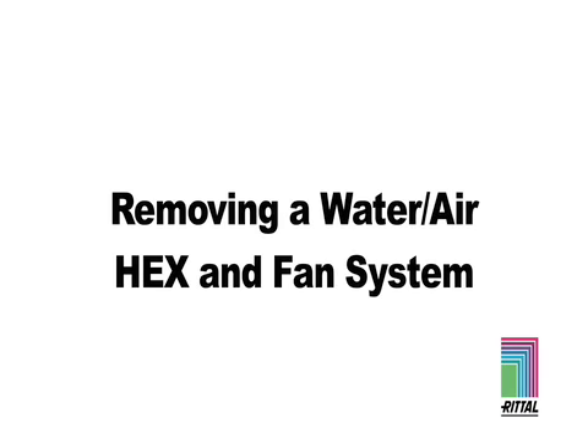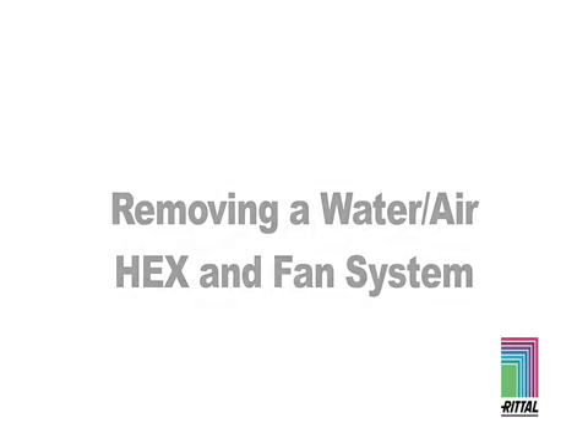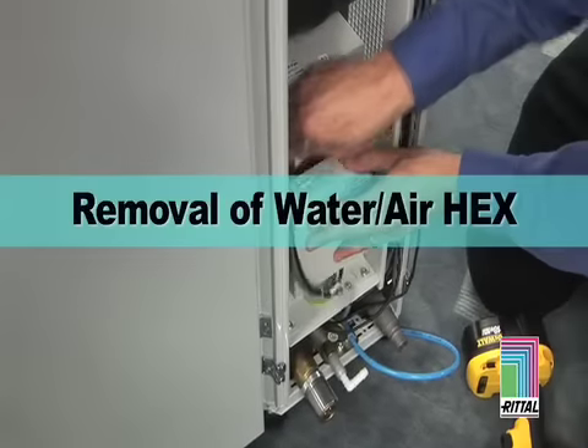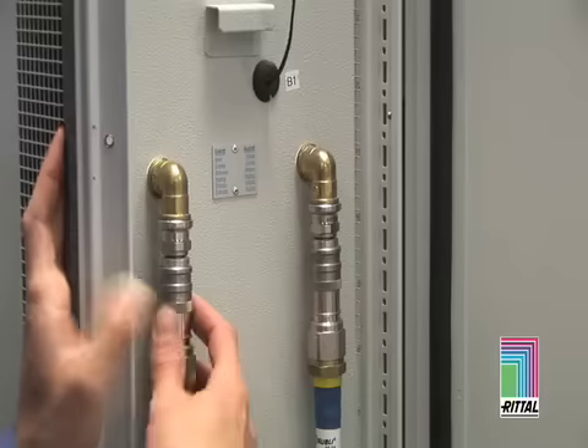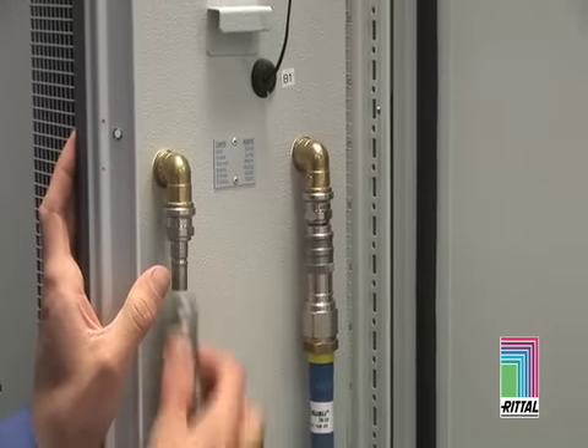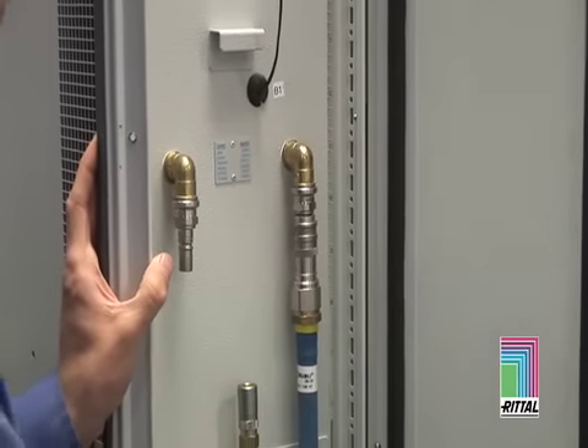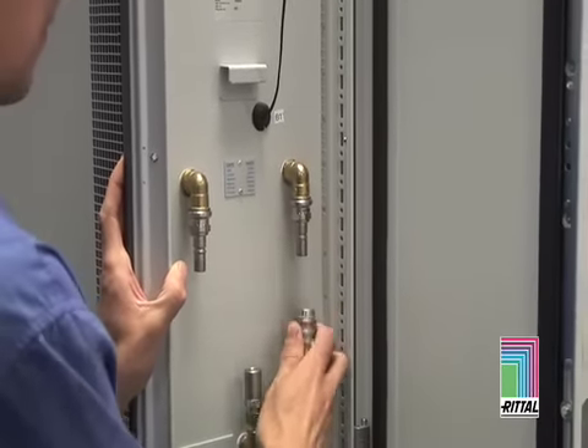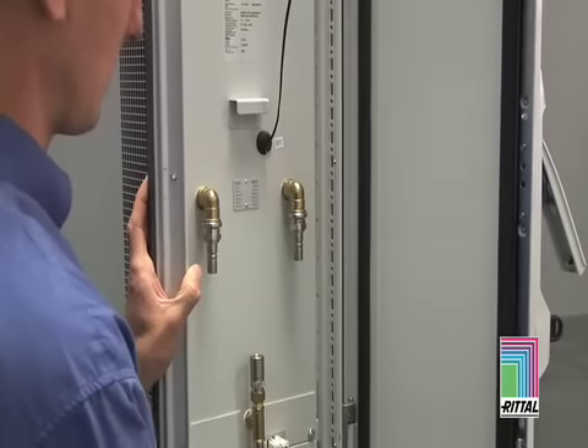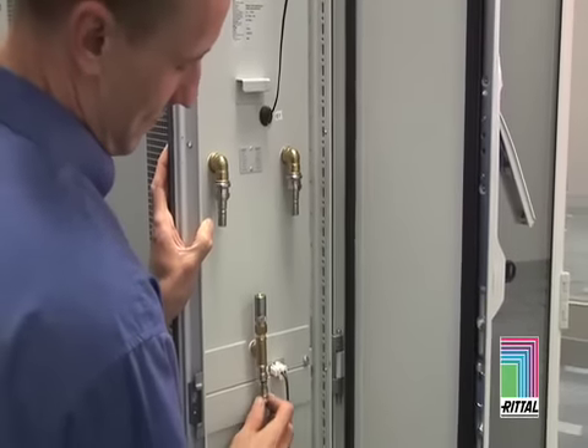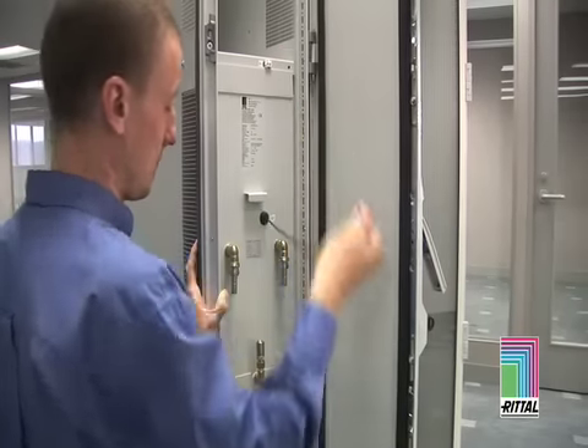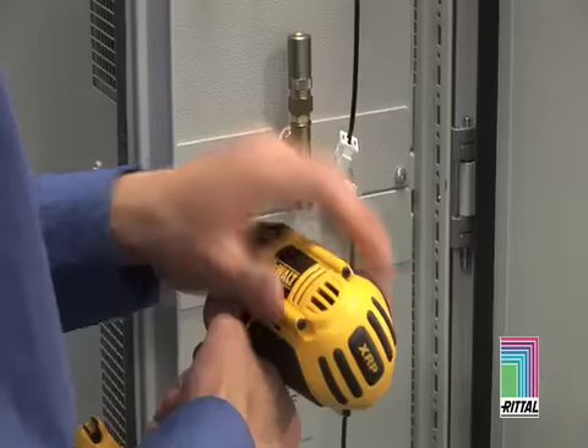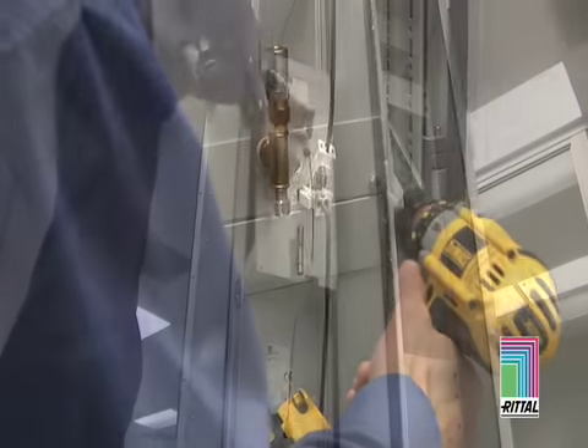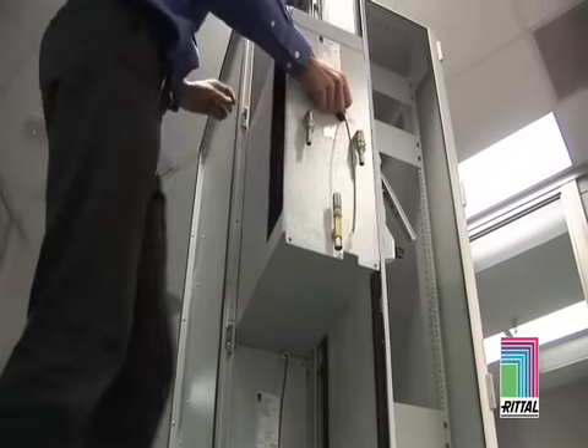Removing a water-air heat exchanger and fan system. Removal of water-air heat exchanger. Removal of the air-to-water heat exchanger requires the user to first disconnect the supply side water lines on the heat exchanger, and then disconnect the return side. Next, the condensate lines are disconnected from the system. Finally, the temperature probe is disconnected, and then the 2 screws holding the hex in place are removed. Then the entire heat exchanger is removed from the front of the unit.